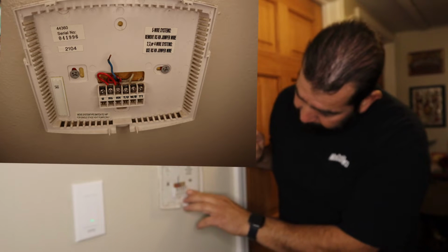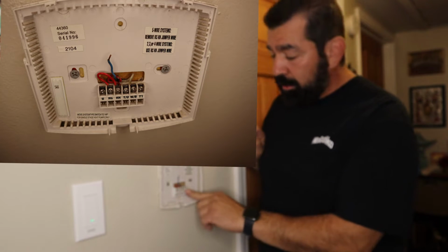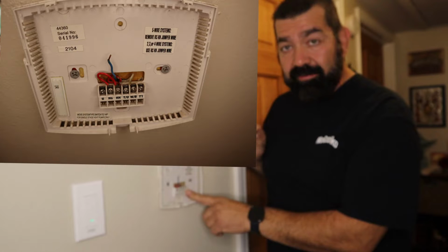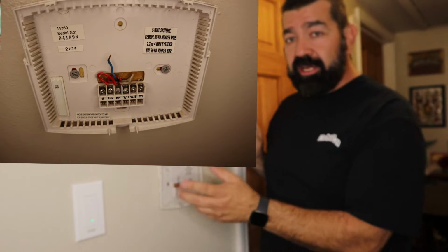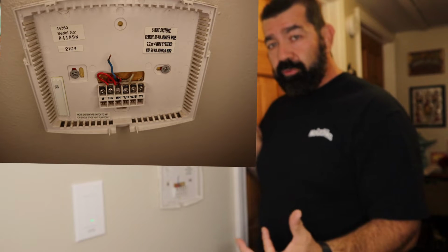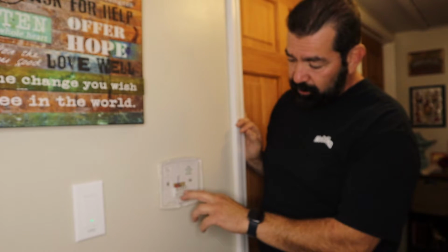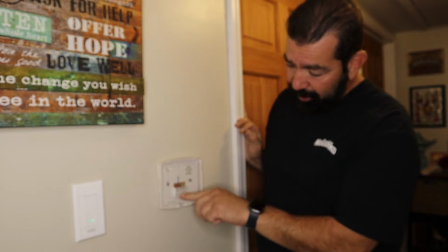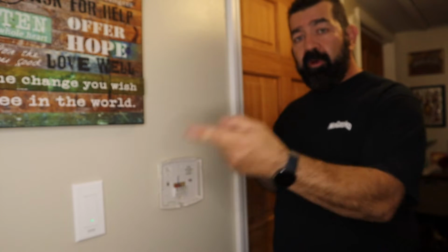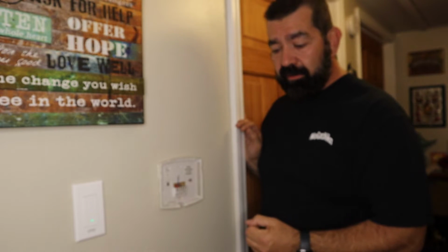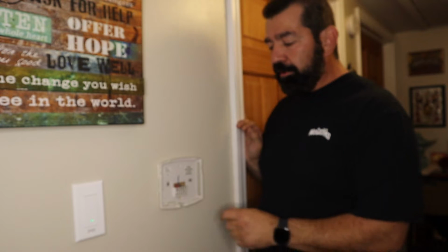If you had cooling, you'd be on the Y wire, and if you had a fan-only setup, that would be G. But I don't have any of that since I have a boiler - no fan, no central air. So I'm only dealing with the white wire and the red wire, and I'll also connect the transformer to give it power.